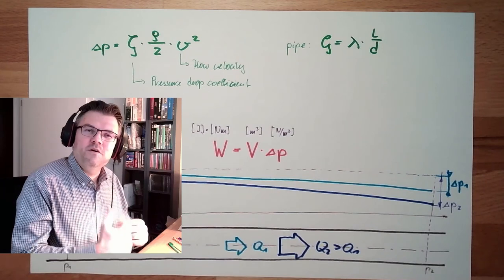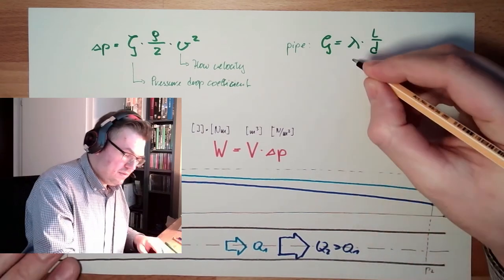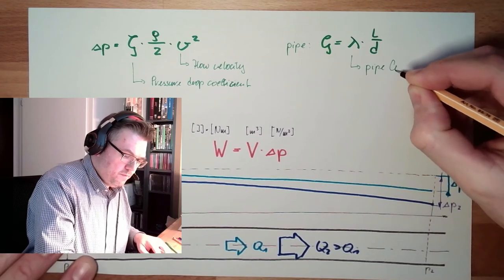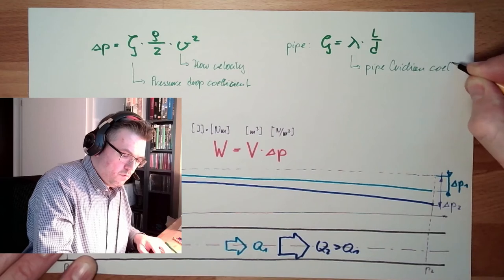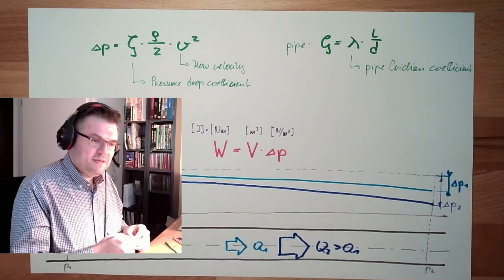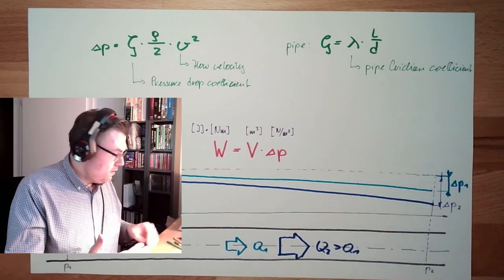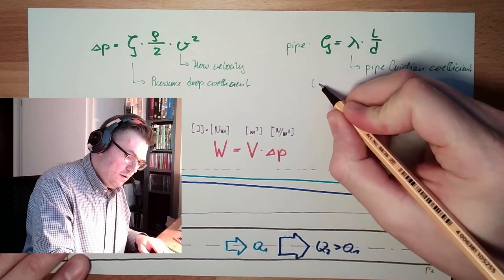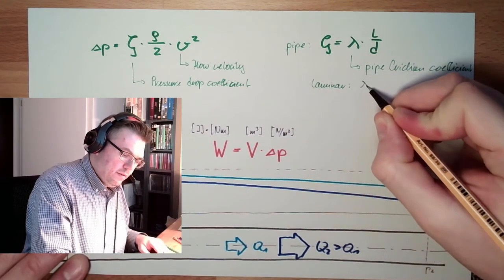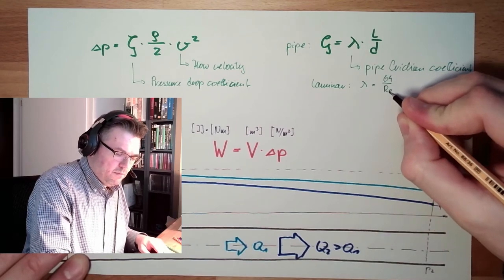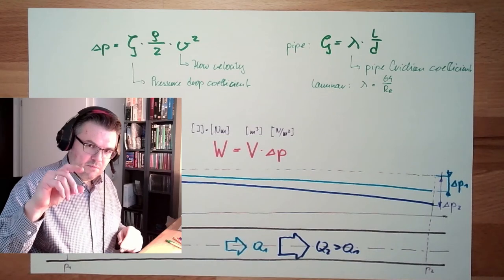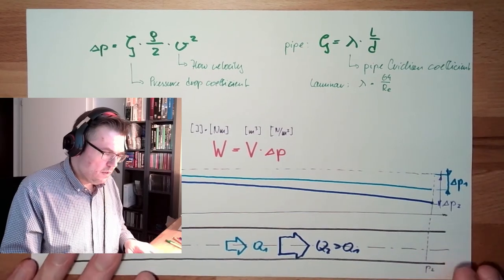This lambda here, this friction, pipe friction coefficient, this is depending on the Reynolds number. And also on the type of flow. If it's laminar flow, we can even give a formula for lambda. This lambda is 64 divided by the Reynolds number. And this Reynolds number we talked last time. This is the stuff where is also the velocity inside, and there is the diameter inside, and there's also the viscosity inside.